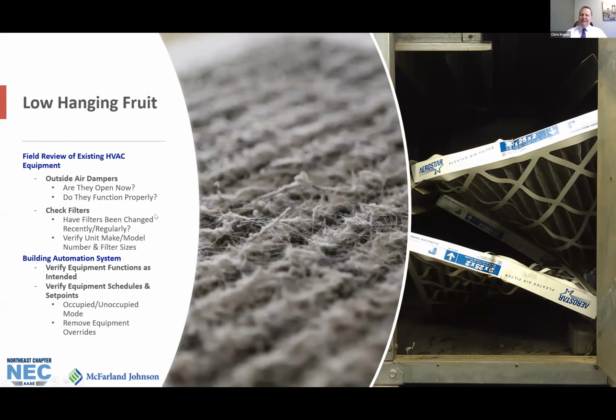Check your outside air intake regularly for potential risks such as exhaust nearby, or proper clearance if accessible by passengers. And for your building automation system, check that the zone and air temperature sensors are calibrated accordingly, and make sure that your occupied, unoccupied schedules haven't been overridden. What I've seen happen is, for whatever reason, maybe it's an extended cold streak or some nuisance fumes being drawn into the unit, someone at some point has closed a damper or overridden a schedule. It's been like that for months on end.